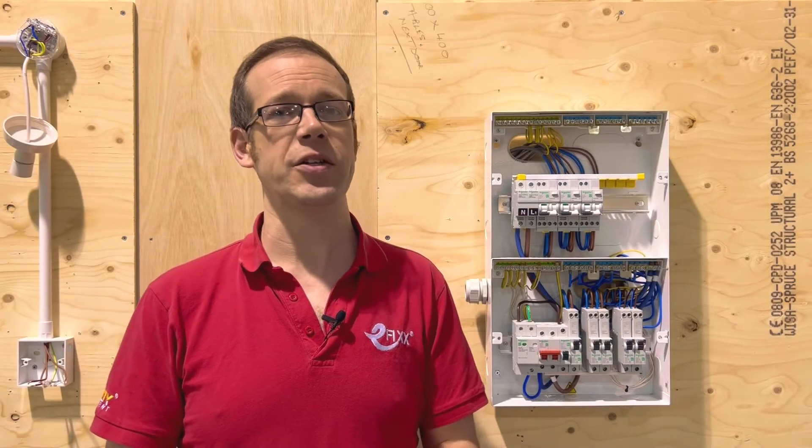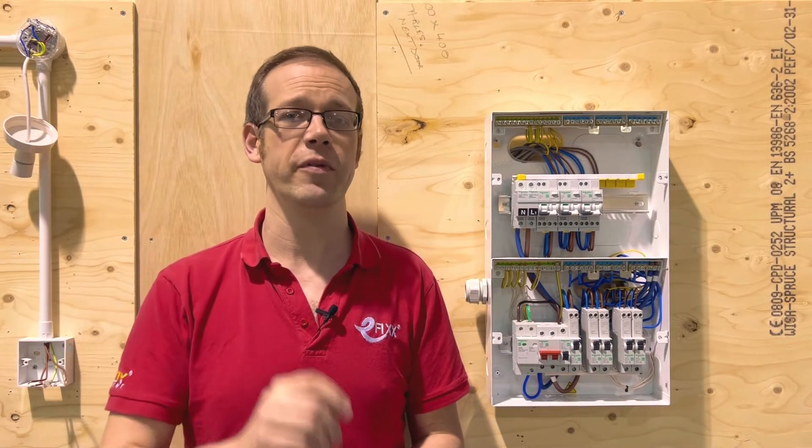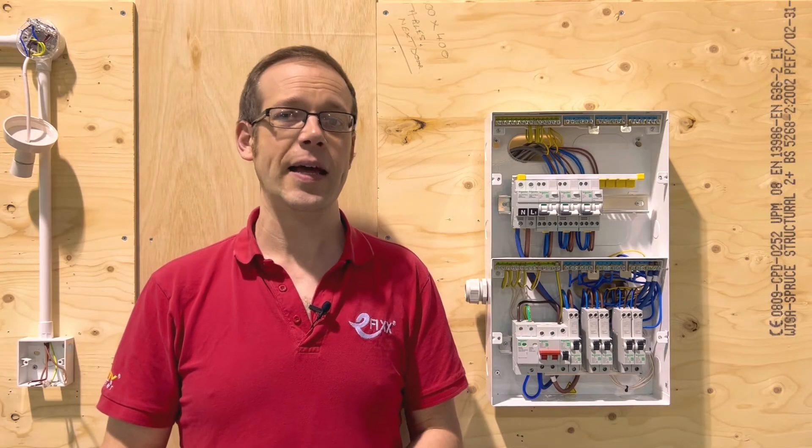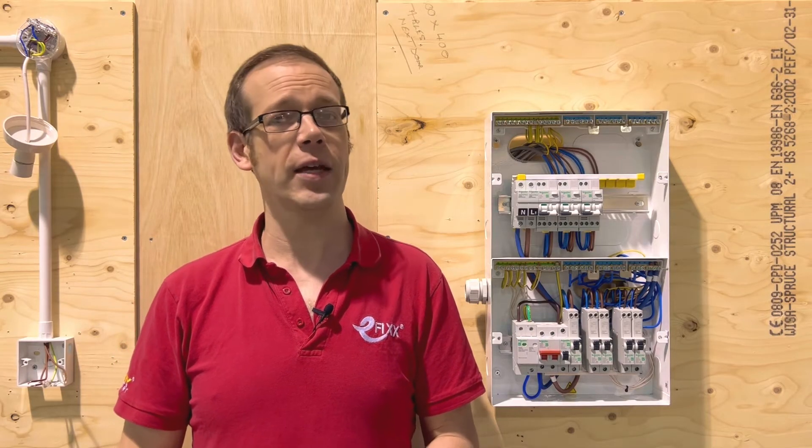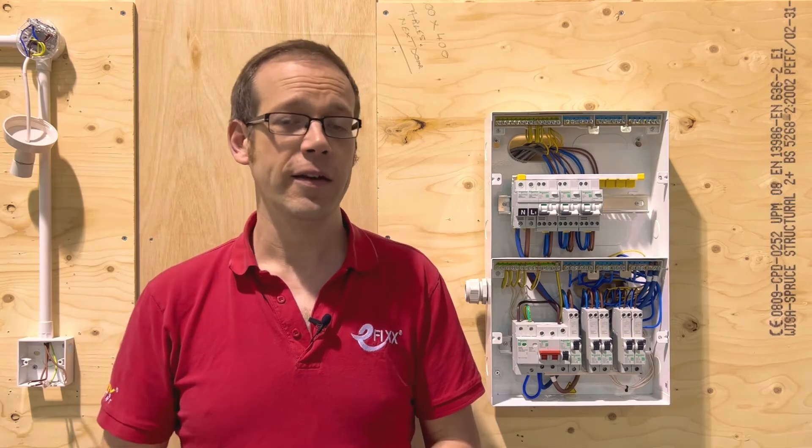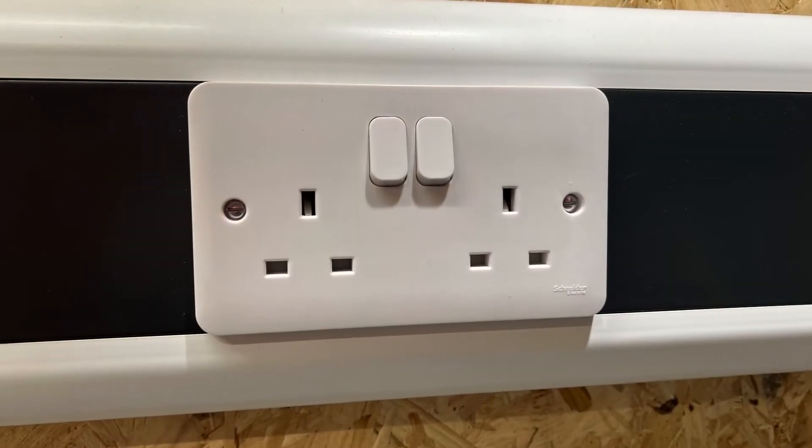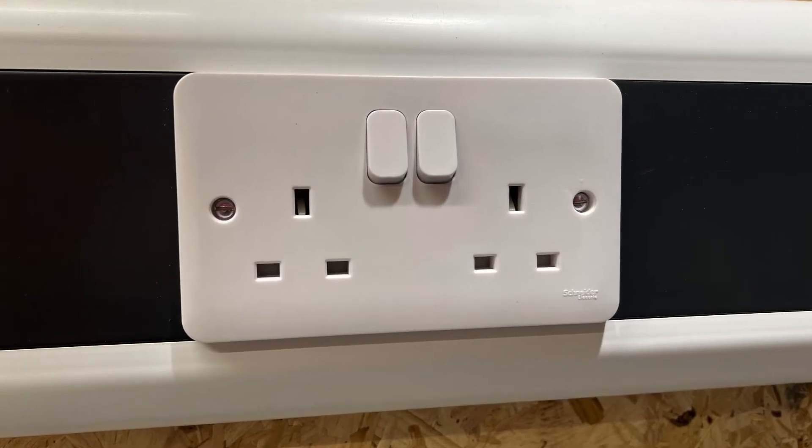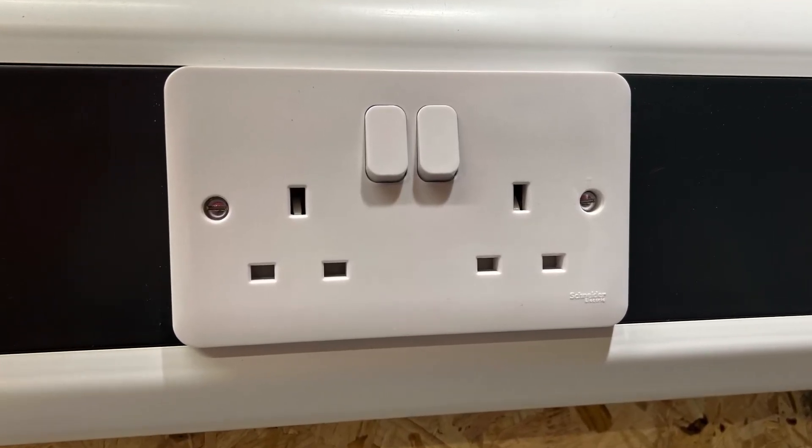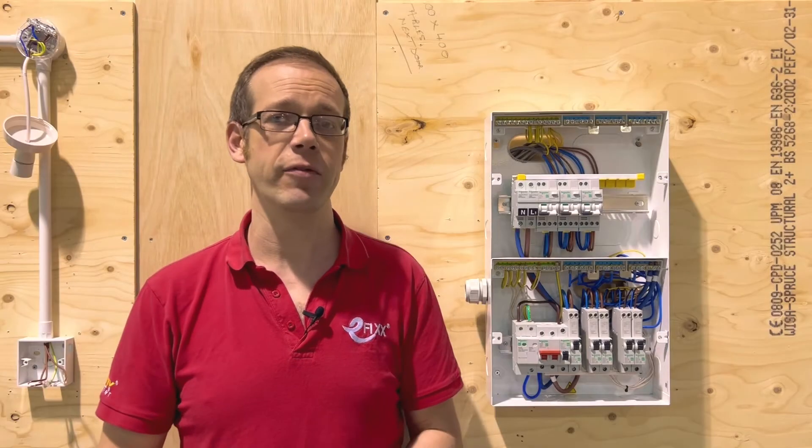So if you're installing circuit protection to these types of properties then you must provide AFDD protection to any single phase circuits supplying socket outlets up to 32 amps in value. So because the standard BS 1363 socket outlet is rated at 13 amps then the circuits feeding them must have AFDD protection in those environments.